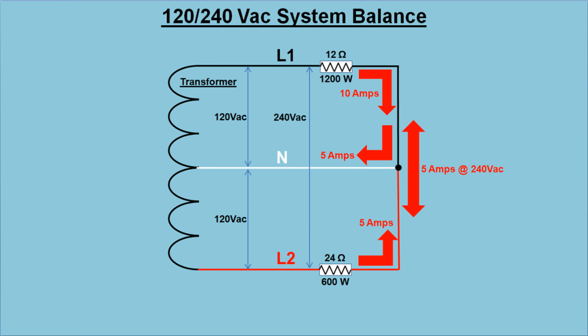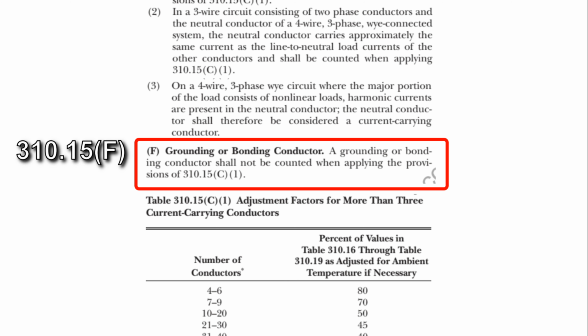Considering that the heating effect of current flow on line 2 and the neutral combined is equal to the heating effect on line 1, the code doesn't consider it necessary to consider the neutral as part of the number of current-carrying conductors for derating purposes. Basically, I interpret it as those two equal one conductor, so only count them as one. So, the grounding and bonding conductors. 310.15f, grounding and bonding conductor. A grounding or bonding conductor shall not be counted when applying the provisions of 310.15c1. These don't count because they aren't current-carrying conductors.